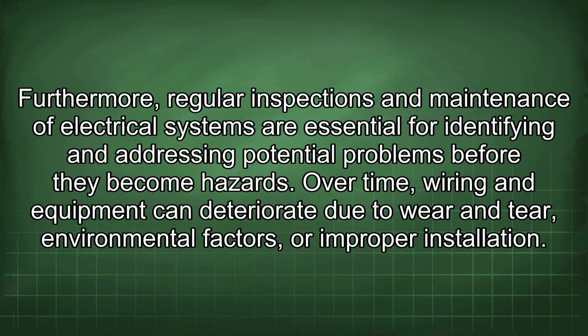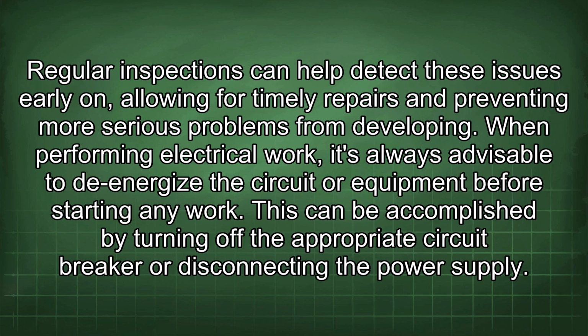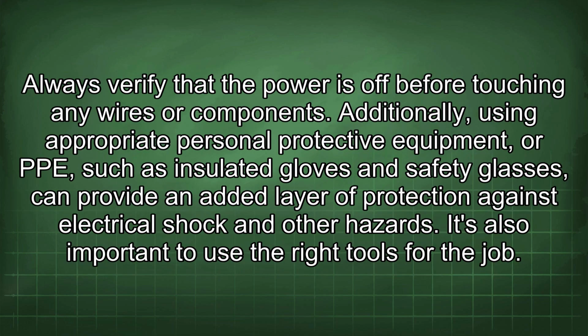Furthermore, regular inspections and maintenance of electrical systems are essential for identifying and addressing potential problems before they become hazards. Over time, wiring and equipment can deteriorate due to wear and tear, environmental factors, or improper installation. Regular inspections can help detect these issues early on, allowing for timely repairs and preventing more serious problems from developing. When performing electrical work, it's always advisable to de-energize the circuit or equipment before starting any work. This can be accomplished by turning off the appropriate circuit breaker or disconnecting the power supply. Always verify that the power is off before touching any wires or components. Additionally, using appropriate personal protective equipment, or PPE, such as insulated gloves and safety glasses, can provide an added layer of protection against electrical shock and other hazards.